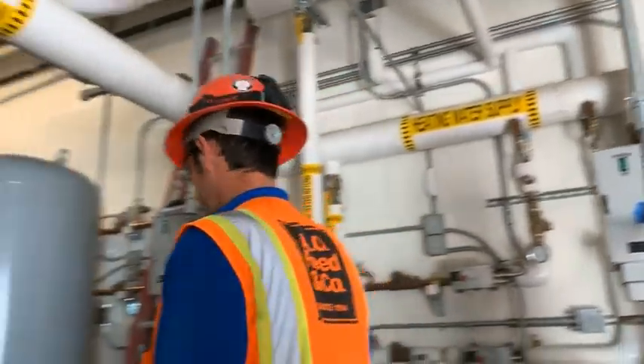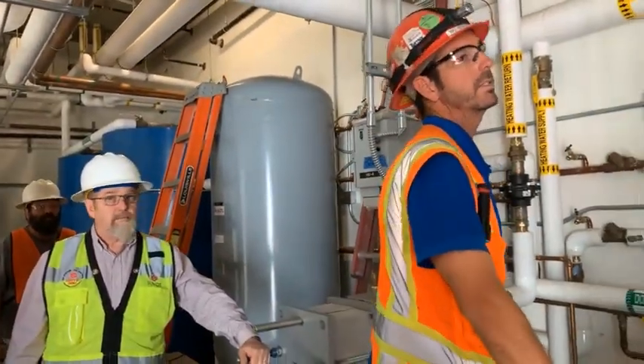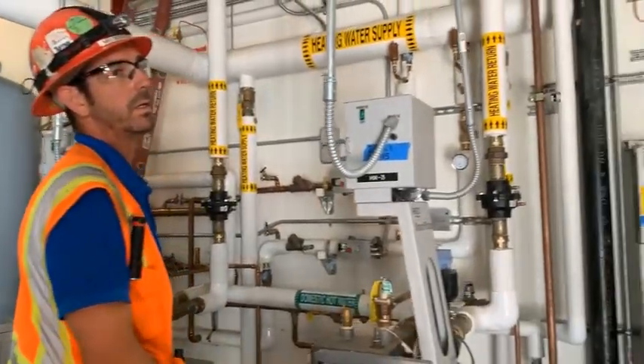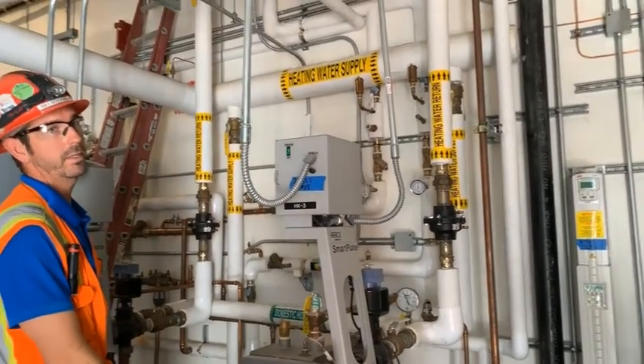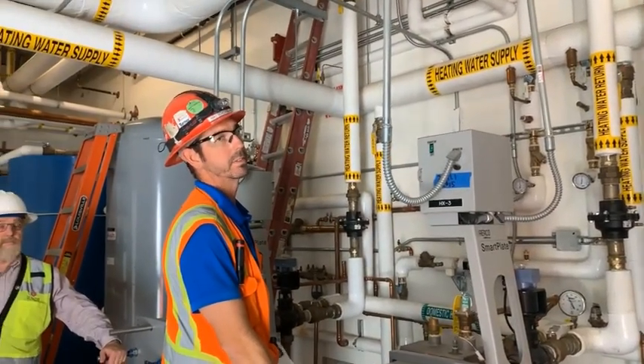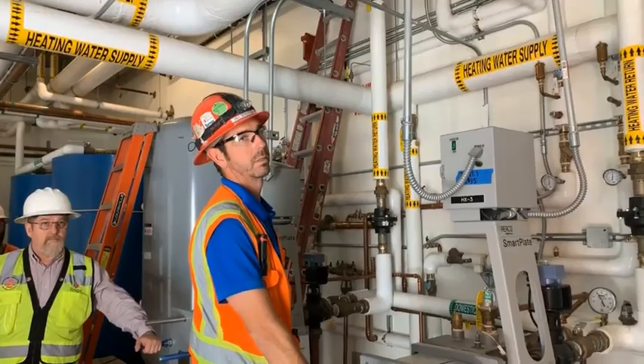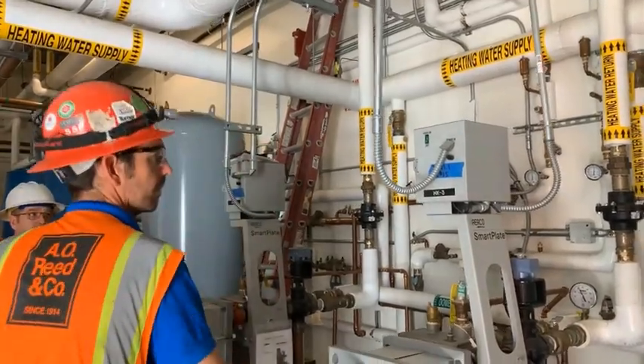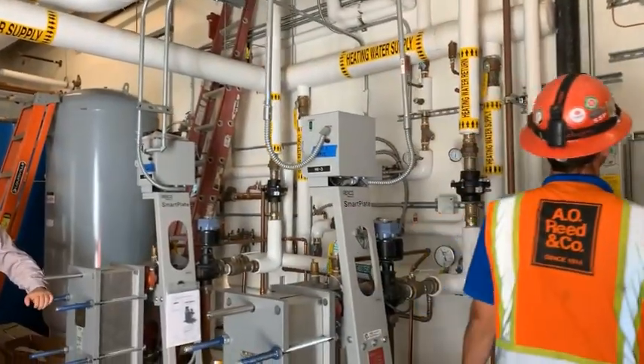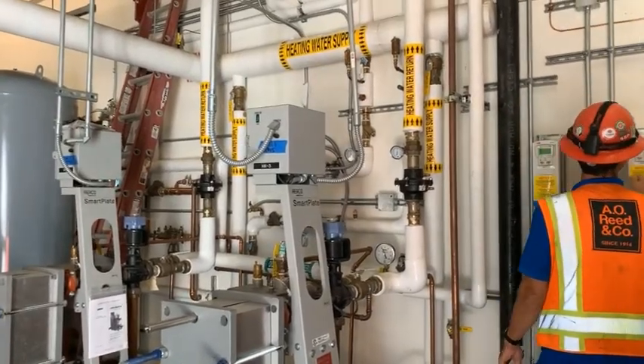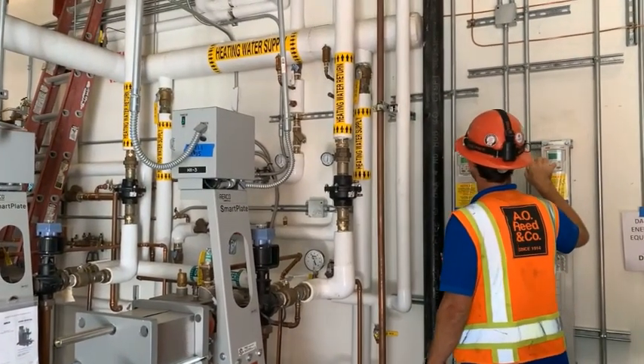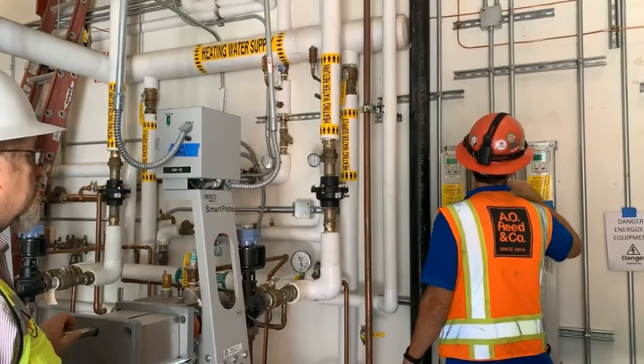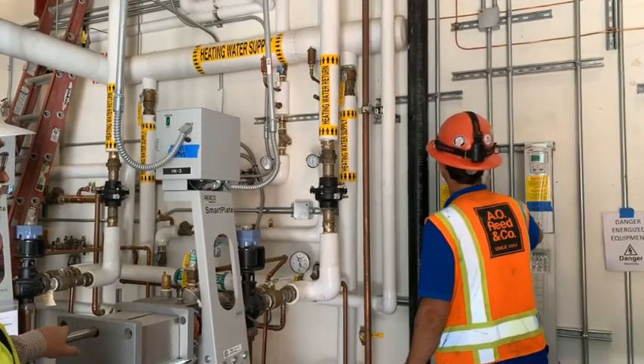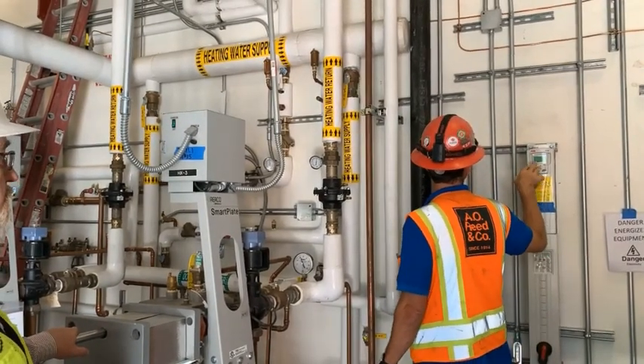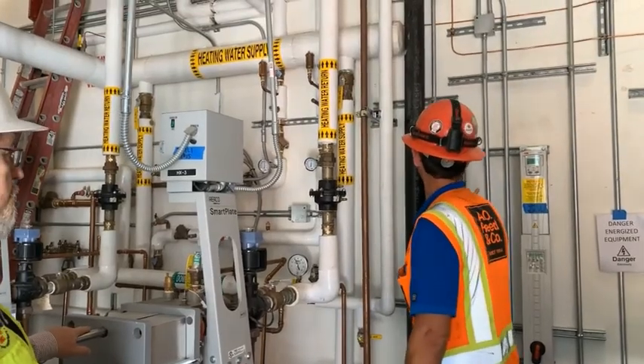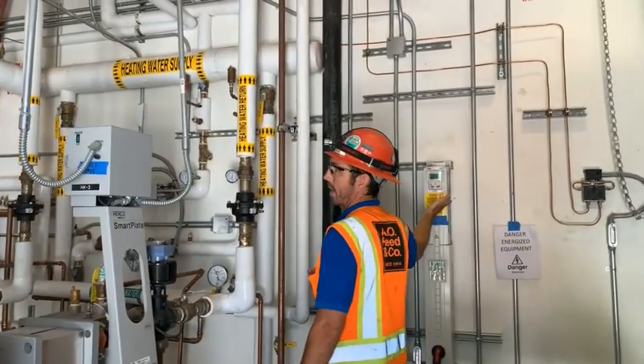Are you doing a lot of testing right now in this building? You're not doing anything over here? Do you know why everything just turned off? No. Somebody's playing with this stuff. We got another pump off. Again, VFDs will do that, but we were in off and auto, so if they were to switch from pump 4 to 3 and this was off, it wouldn't turn on.